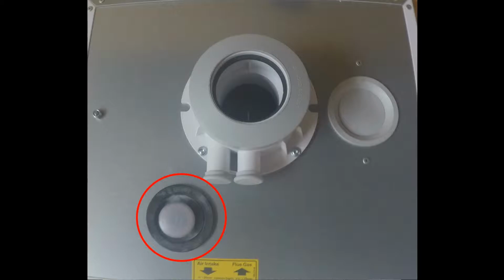If you take a look at the top of your boiler, this is where you will find the connection for your boiler pressure relief. Very important that you know that you need to externally support this pipe so the weight is not laying on the boiler itself.